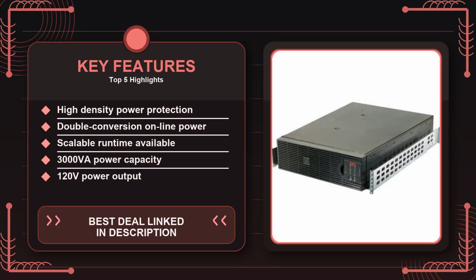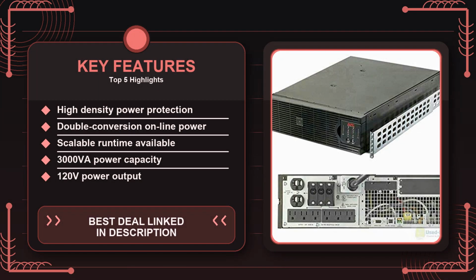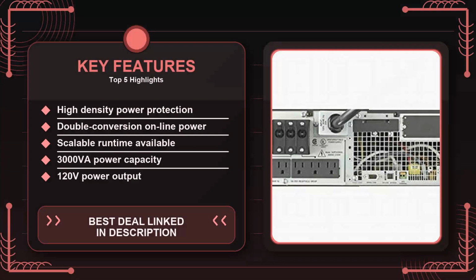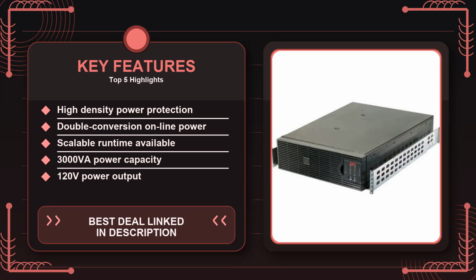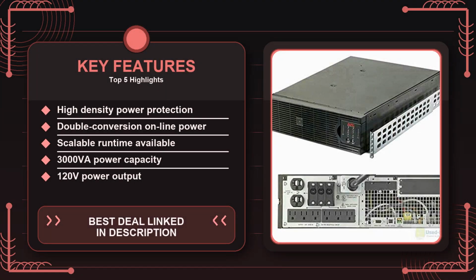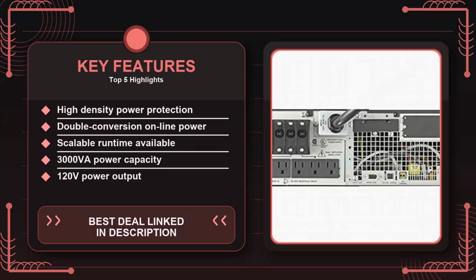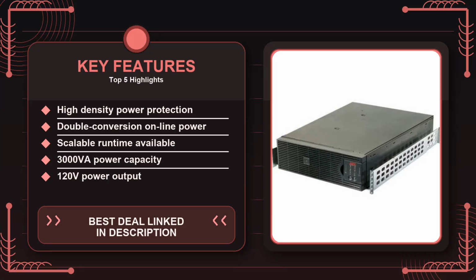Battery runtime is another key factor. The UPS ships with a sealed lead-acid battery that can be swapped for an external extended runtime module. In a typical office server room, the default battery provides roughly 10 minutes of backup at half load. That window is usually enough for an automated shutdown script to fire, protecting data integrity and preventing hardware damage. If you need longer runtime, say, to keep a network hub alive while a generator starts up, you can add a secondary battery pack without replacing the whole unit. That modularity is a concrete cost saver because you only pay for the extra capacity when you truly need it.